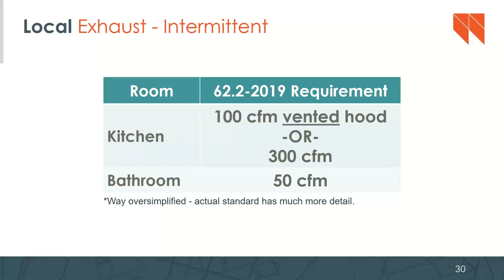So you need to take into account things like elbows and the length of the run, right? All of this stuff is referred to as the total effective length. There are calculations to come up with that total effective length, and then you want to make sure that the bathroom fan can do that.